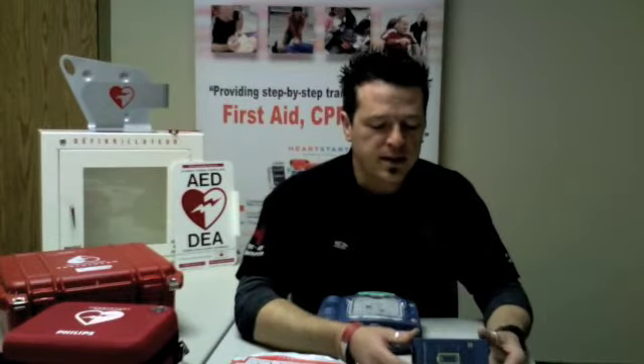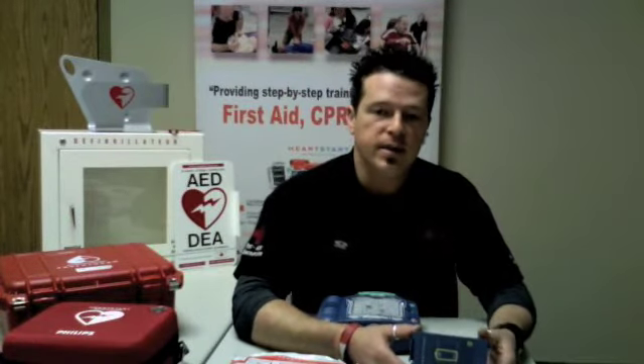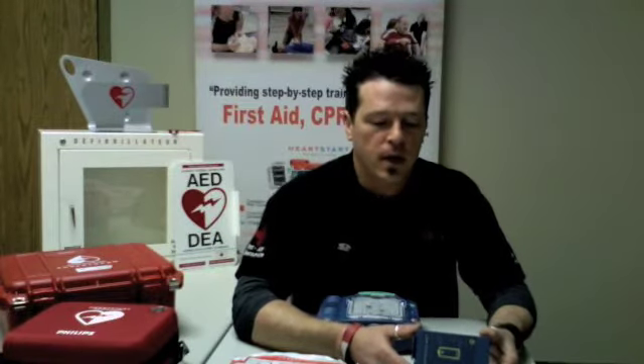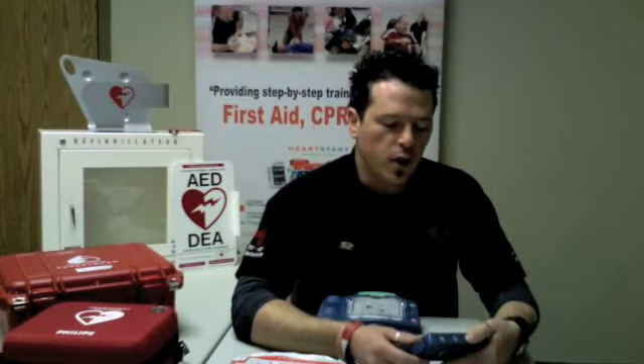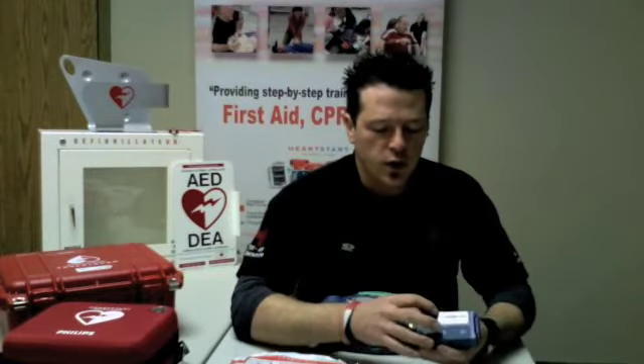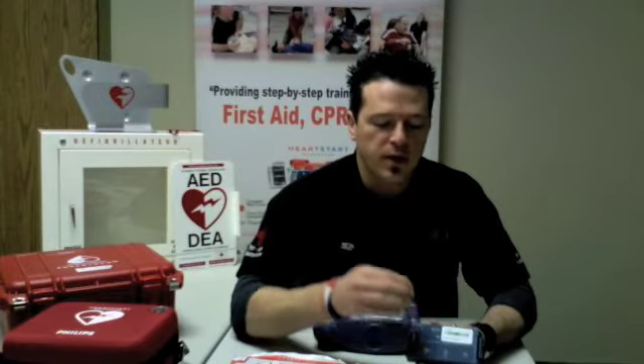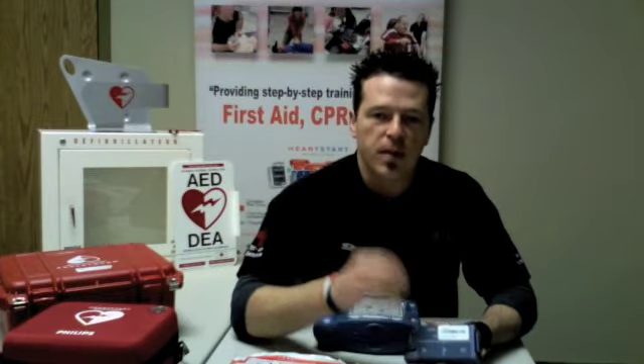In terms of the battery, however, it's a little bit different. The battery itself has a 5-year shelf life and is typically good for 4 years in the defibrillator. So in other words, the install before date of this battery is 01/2011. So as long as the battery is installed in a defibrillator before January 2011, from that point on the battery will be good for 4 years.